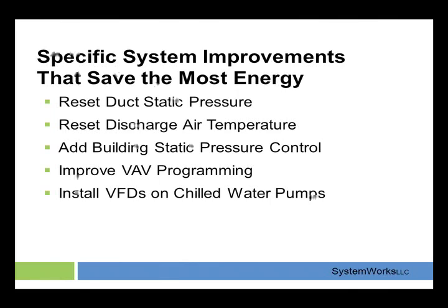VFDs, variable frequency drives, is what VFD stands for. And what they had at this building, and I'm sure many of your buildings, is pumps, hot water pumps, chilled water pumps that run constant volume. They run 24/7, or even if they run 8 hours a day, they run at full speed, 60 hertz. Well, what a VFD does, you add a variable frequency drive and you can slow that pump down. The speed of that pump can modulate based on demand. Very similar to what we were talking about with the heating and cooling. If the building needs more pump flow, the pump speeds up. But if the building becomes satisfied, the pump can back off, and it saves a tremendous amount of energy.